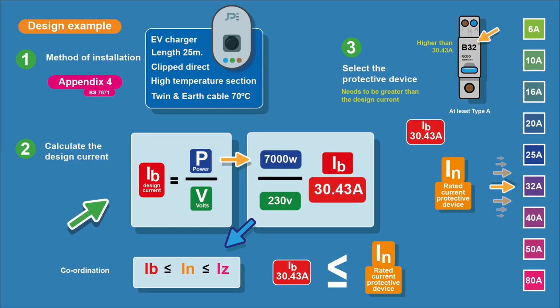Next we calculate our design current. This EV charger is 7000 watts. To get the design current, we divide the power — 7000 watts — by the voltage, which is 230 volts, and we get our IB, our design current, of 30.43 amps.